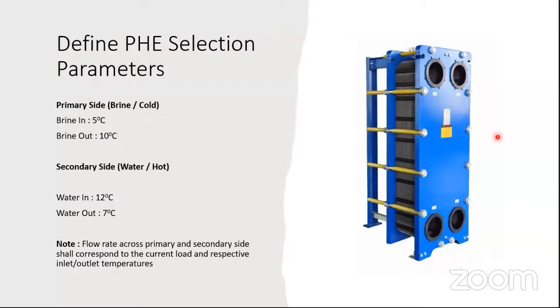Now we also need to define the PHE selection parameters, because the PHE guy also needs to know what parameters will be required. So on the primary side, the PHE will only come into picture when there is cooling happening. So 5 degrees centigrade brine in and 10 degrees centigrade brine out, which is our primary side, the cold side, and that is the brine side. The secondary side is our water side on the other side, which is hotter. So the water in is 12 degrees centigrade, water out is 7 degrees centigrade, and we will also mention the corresponding flows on both the sides, because the load on the PHE will be the load on the brine circuit. So according to the load, the corresponding flow can be given on both the sides.